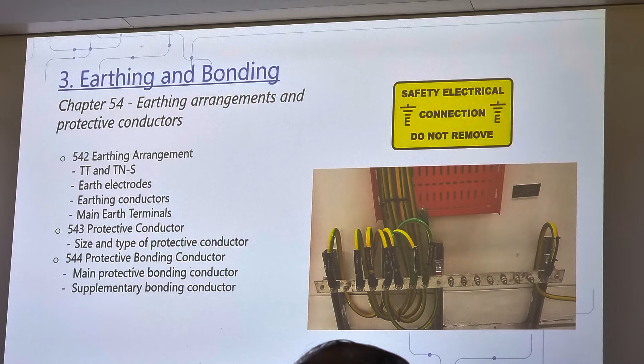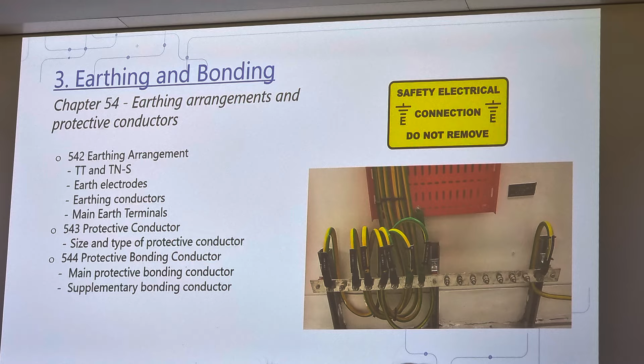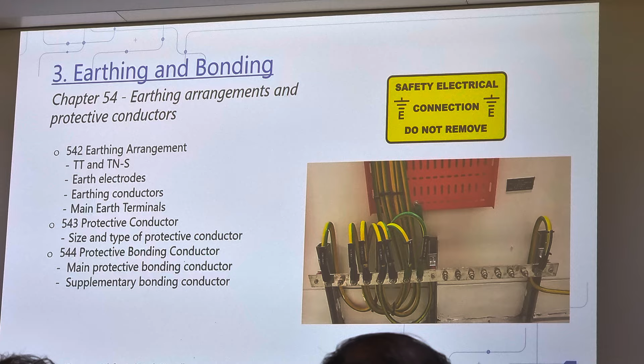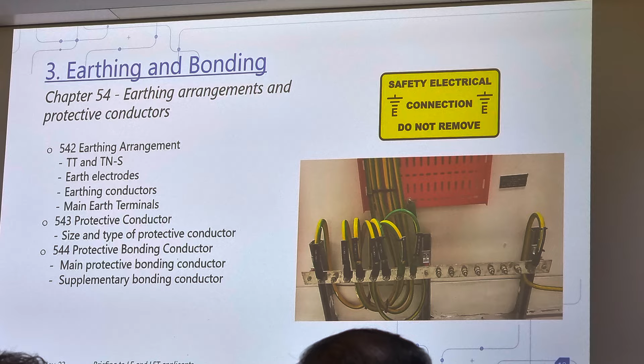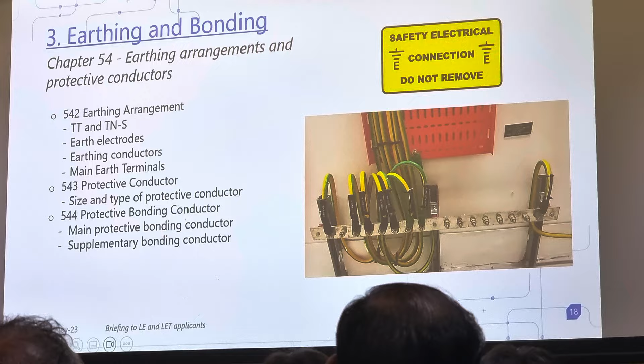Now, 544 talks about bonding. So, separate to 543, which is protective conductors, it goes into details of protective bonding conductors. It talks about the main bonding conductor, which is the main one, the bonding to the main earth terminal. It also talks about supplementary bonding. So we want to know more because, as I said, you need all these conductors to work together to achieve the automatic disconnection of the protective device.